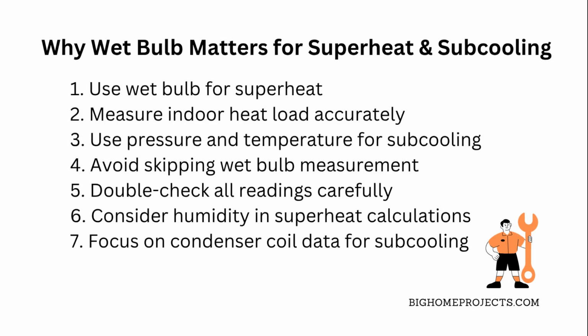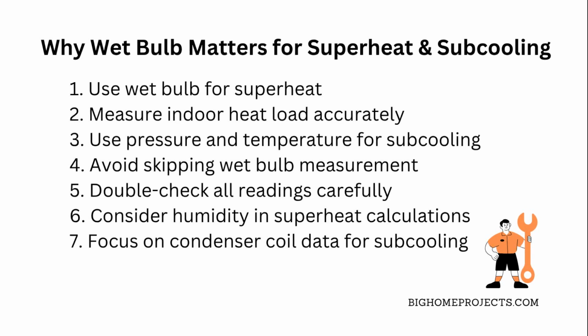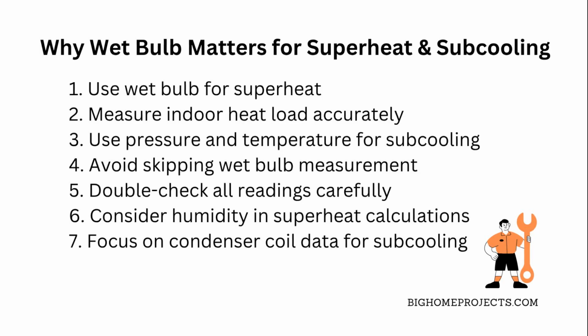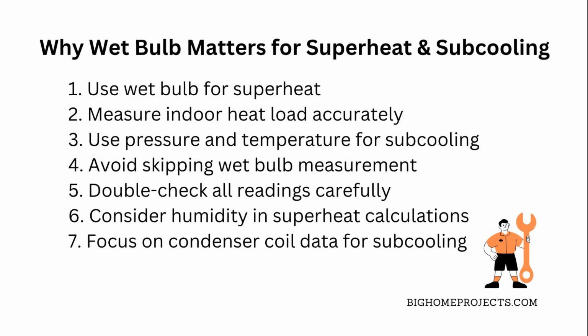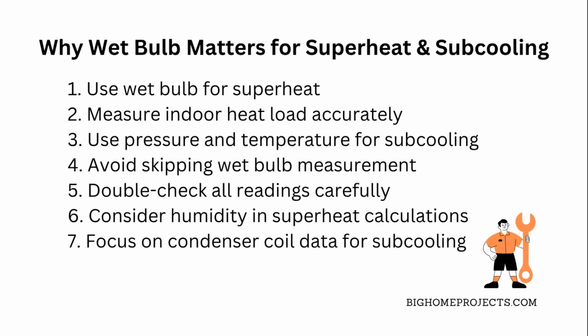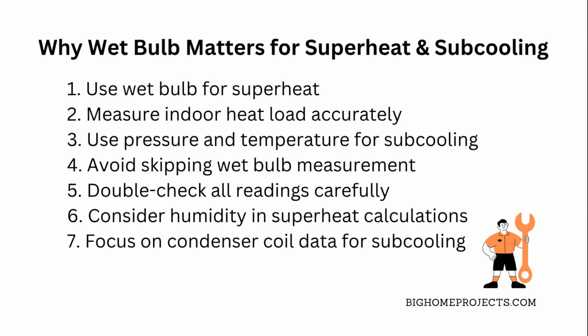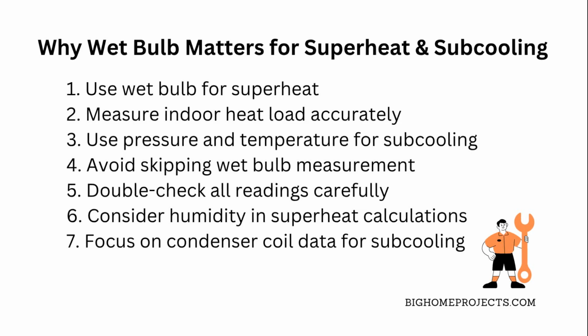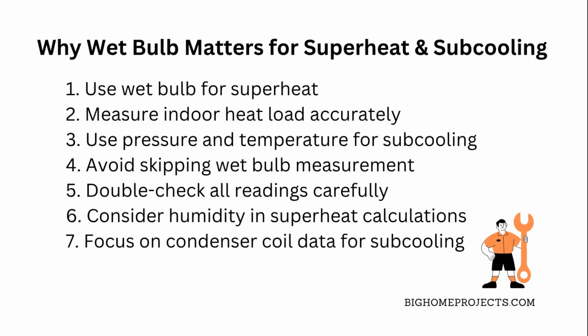On the flip side, subcooling is all about how much the refrigerant is cooled below its condensing temperature, and that's based just on pressure and temperature readings from the condenser side. No need to bring in wet bulb temps here, since it's not about indoor heat, but more about how well your condenser is doing its job. If you skip using wet bulb for superheat, you're basically flying blind on how indoor conditions affect your system, and ignoring pressure, temp for subcooling means you might miss signs of overcharging or other issues.